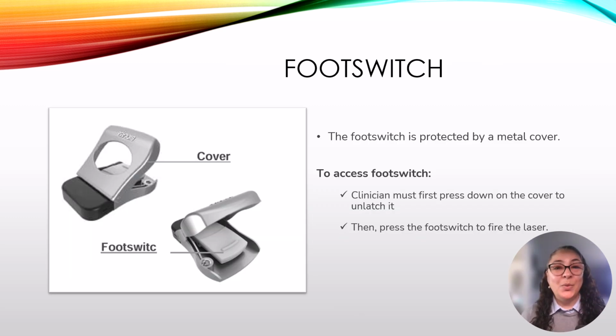The foot switch can be wired or wireless. This particular model is designed for wireless operation and is powered by 2 AAA lithium batteries, which are installed and paired with the base console before shipment from the factory. Energy is emitted only when the clinician presses down on the foot switch while the laser is in ready mode.